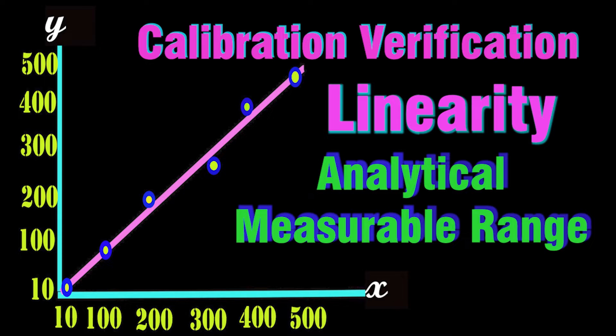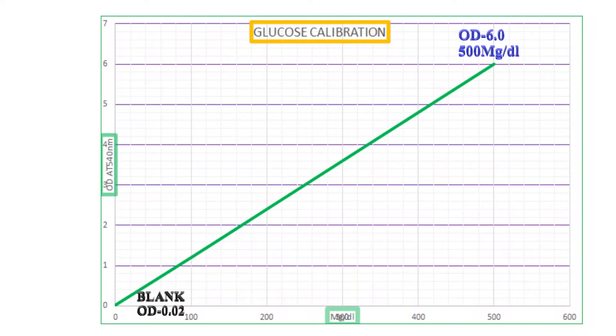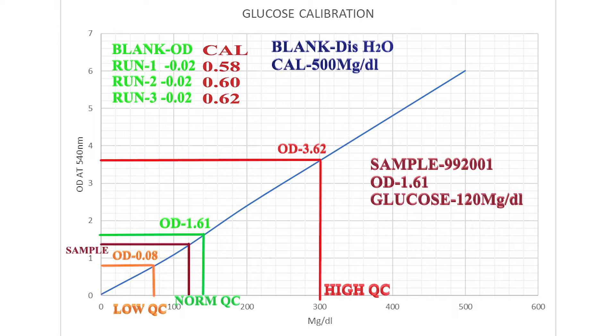Calibration is the process of establishing a correlation between the measurement signal generated by an instrument and the true concentration of analyte in the calibrator. Calibration is setting the analyzer with the reference point so that patient samples are compared to produce test results. Simply, it is telling the instrument how to read analyte concentration from the patient samples.